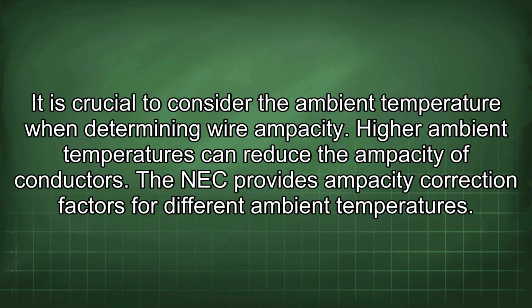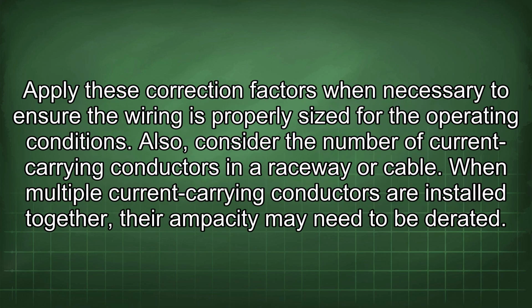It is crucial to consider the ambient temperature when determining wire ampacity. Higher ambient temperatures can reduce the ampacity of conductors. The NEC provides ampacity correction factors for different ambient temperatures. Apply these correction factors when necessary to ensure the wiring is properly sized for the operating conditions.